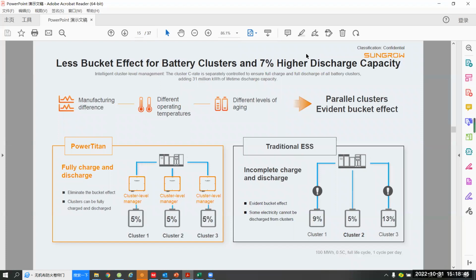But for Sungrow's PowerTitan series system, we use a cluster level manager for each battery rank. This allows it to detect the capacity status of each battery module and rank, and adjust the charging and discharging power for each rank to keep capacity levels equal, allowing the system to charge and discharge fully. Because of this cluster level management, it reduces the bucket effect of the battery pack and increases discharge capacity by 7%.